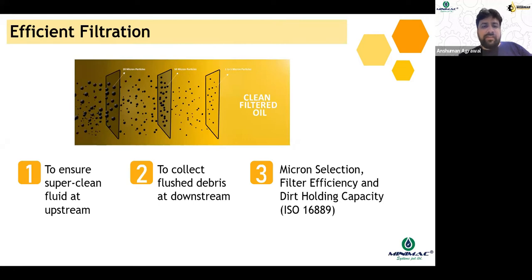As flushing is a time-bound activity and has to be done very fast because there is a project for completion, you do the selection of filtration based on the ISO 16889 standard. And for that, you need a good beta-rated filter. You also need high dirt holding capacity.